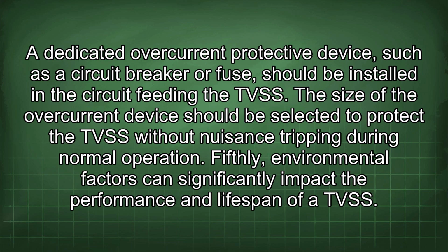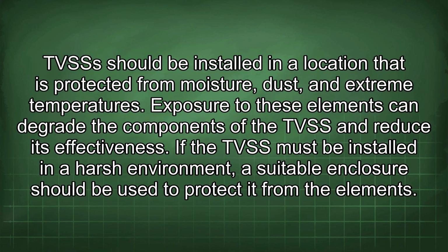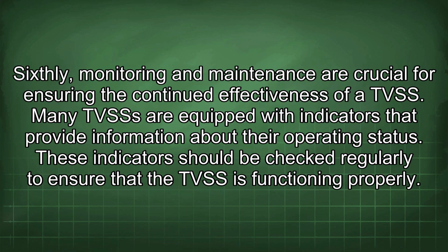Fifthly, environmental factors can significantly impact the performance and lifespan of a TVSS. TVSSs should be installed in a location that is protected from moisture, dust, and extreme temperatures. Exposure to these elements can degrade the components of the TVSS and reduce its effectiveness. If the TVSS must be installed in a harsh environment, a suitable enclosure should be used to protect it from the elements.